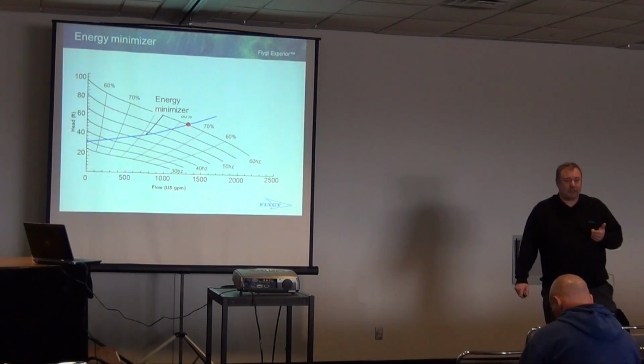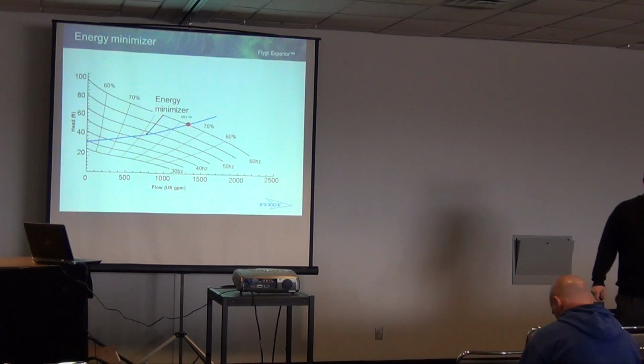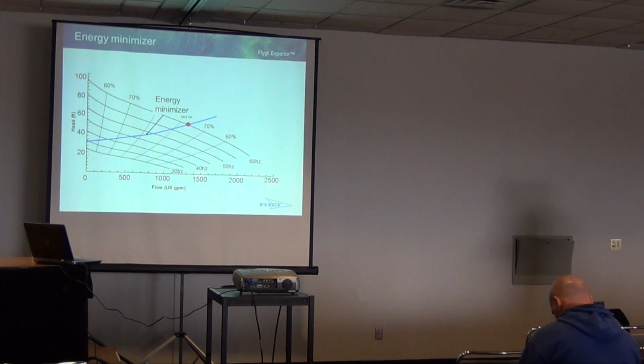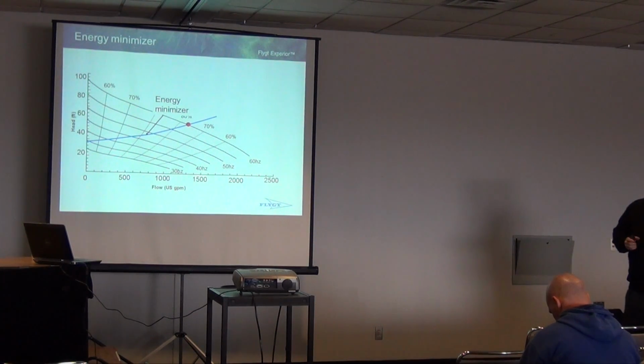But with the sump cleaning functionality built into them and bringing them down to snore, and that's a good point because these units are smart units, they recognize your incoming flow, and if you do have a peak wet weather event, it's going to ramp up and run at a higher speed and then adjust back down. So when you put a mixed flush valve on one of the pumps right now, that differentiates the pumps. But they're working on building that functionality into it, so right now, no.